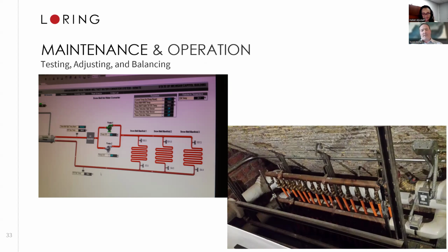When we physically inspected the system, in the right-hand picture you can see 2 small metal boxes on the far right-hand side of that photo. Those are the temperature sensors represented on one of these circuits. We identified which pipe header was having the problem spots out in the snow melt walkways. Looking at these sensors, you'll notice each one of those orange pipes is a separate independent circuit from the main header circuit, so each of those has to have proper water flow as well. We were getting the appropriate aggregate temperature at the sensors, but there was a single circuit from that header that was actually deficient on flow. And I'll let you go to the next slide.